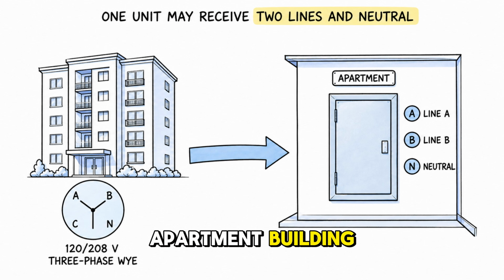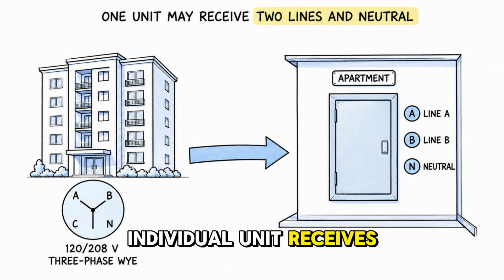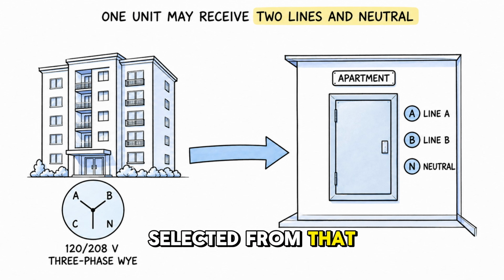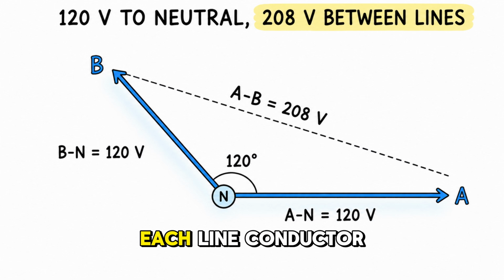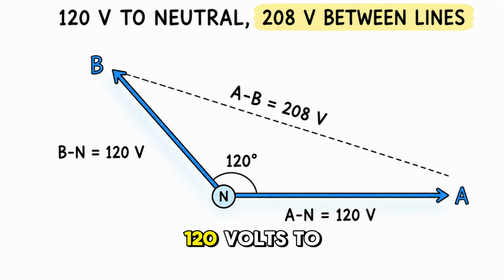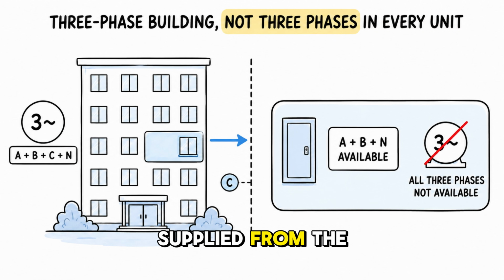In a large apartment building, the main service may be three-phase, while an individual unit receives two line conductors selected from that system, along with a neutral. Each line conductor can provide 120 volts to neutral, while the voltage between them may be 208 volts. The apartment is supplied from the larger three-phase system, but all three phases are not available inside the unit.